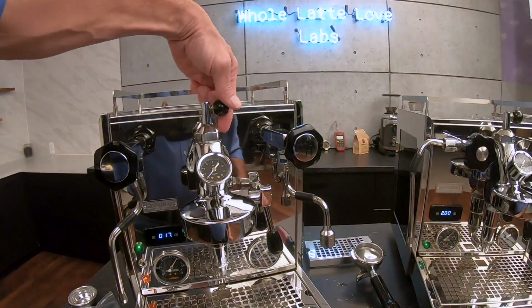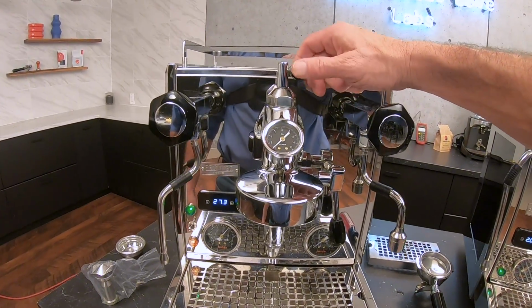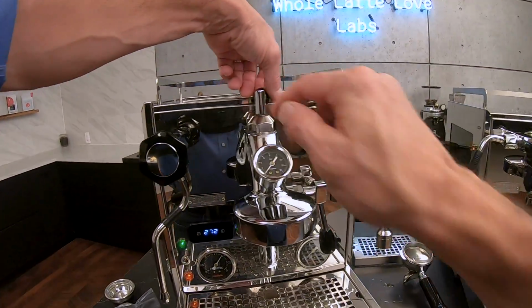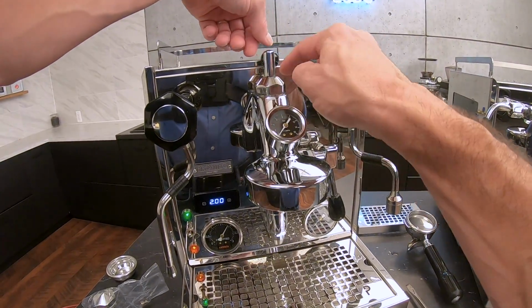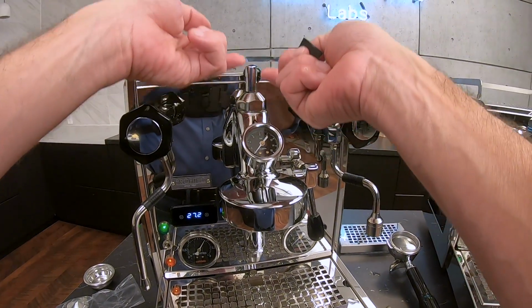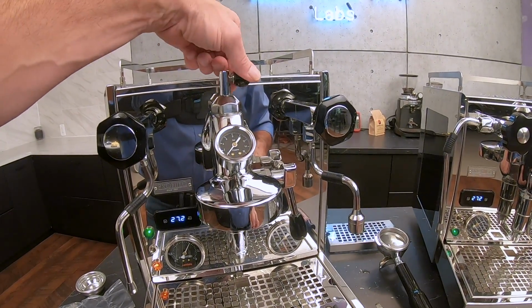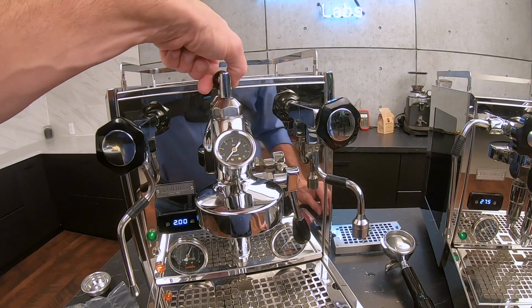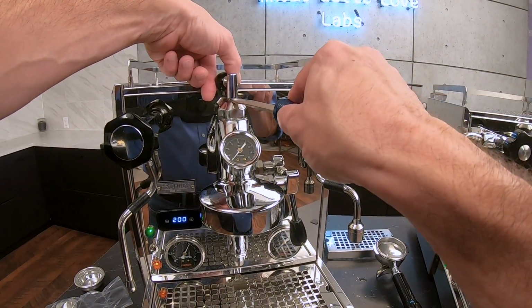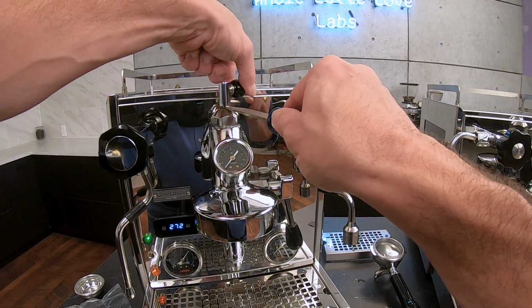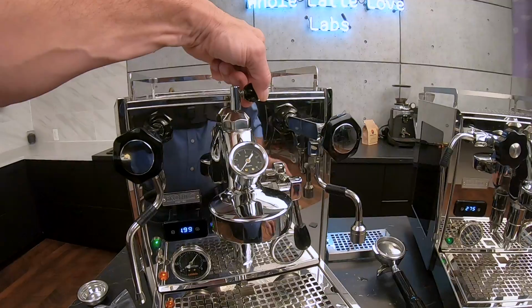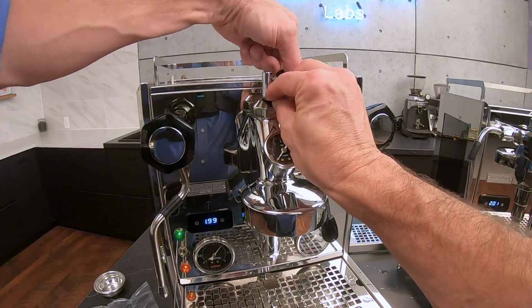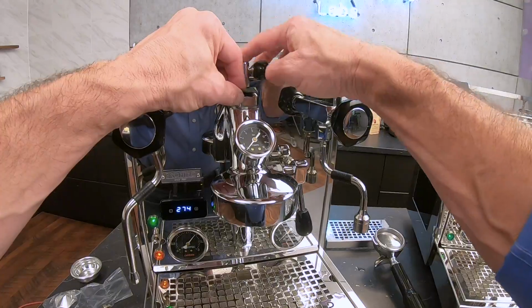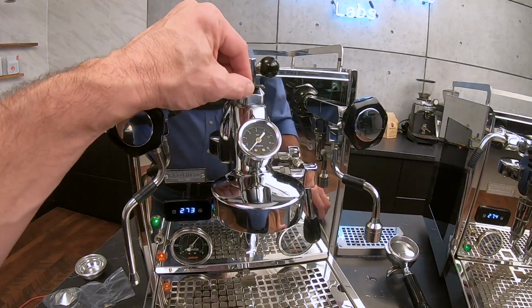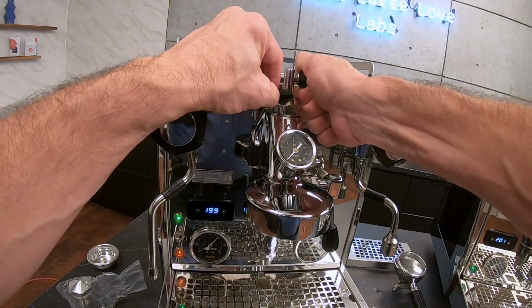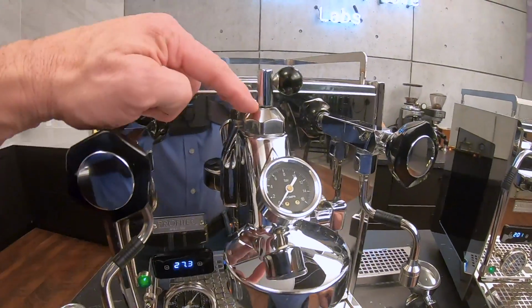To do that, you're going to loosen this. So this knob turns out a little bit, and then you're just going to turn this. What you need to have is a little space in between the sleeve here and the top of the mushroom valve nut. If you don't have that space, you may not be able to fully close the valve. So what I want to do is turn it out a little bit, lift this sleeve up very gently with a screwdriver here. I'm going to go fully closed. I can't move it anymore, maintaining that space. Then I'm going to use something. I've got a little wad of tape here. I'm going to sit it in here, just make sure I keep that space, because you see how that dropped down a little bit. You give it just a little tap. Don't do too much. Then really crank that guy down, and you'll maintain the space in here.